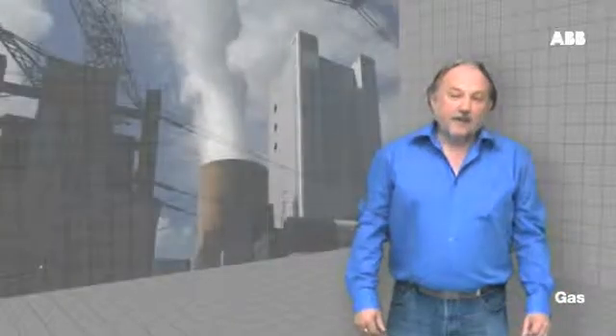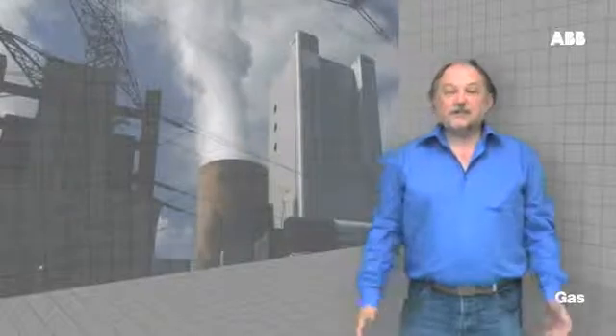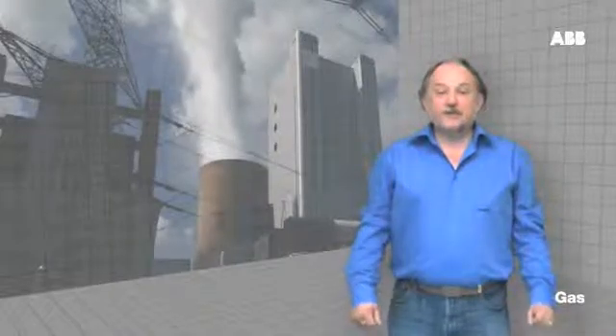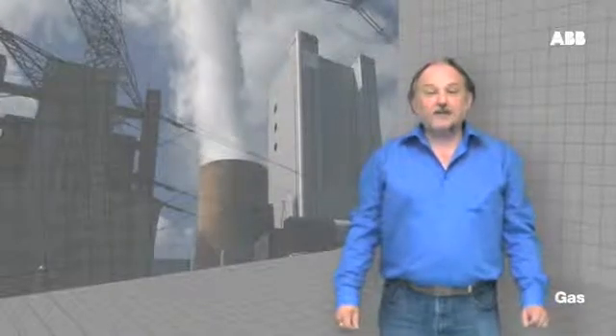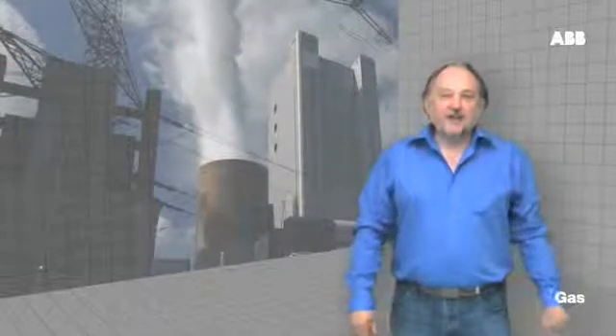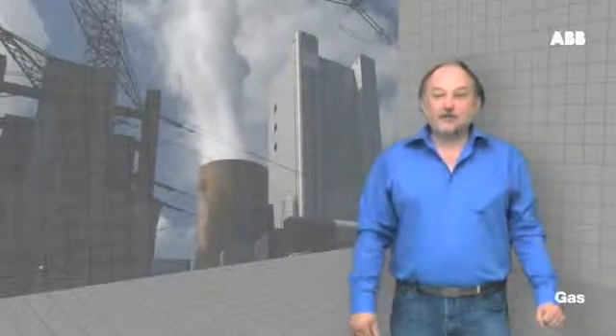In some areas of application and with some older equipment, standardised cubic feet are used, or SCF. These are expressed as if the gas is measured in cubic feet at 60 degrees Fahrenheit and one atmosphere. It's critical when making or comparing volumetric gas flow measurements to establish whether you are talking about actual, normal, or standard units.